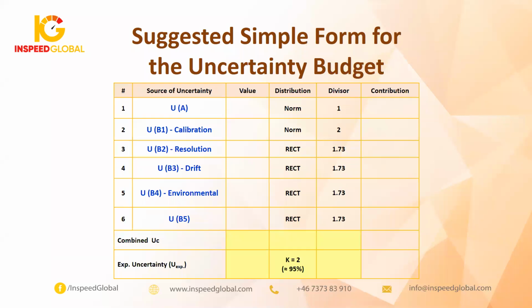Again, to get the resolution of your equipment, take a ruler as an example. The smallest value you can read is 1 millimeter. So you will take 0.5 of this value, so 0.5 millimeter, and after that you can divide by 1.73. Another example, if resolution is 2, you can take half of 2, which is 1, and divide 1 by 1.73 to get the contribution of resolution.